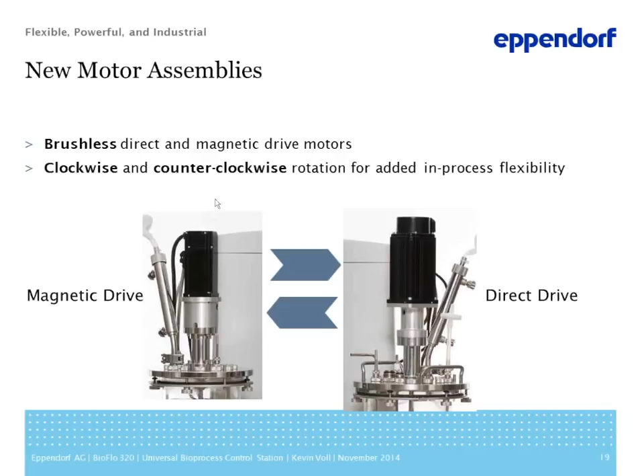In our magnetic drive motor assemblies, we now offer 3 magnetic drive motor assemblies, all using the same base motor, but with 3 different magnetic couplings for 3 different magnetic drive vessels. Our autoclavable vessels have an assembly specific to them. We offer assemblies specific to our single-use vessels, including our larger single-use vessels for the BioBLU 5, 14, and 50, and also an assembly specific to our BioBLU 1 vessels. Because they use the same base motor, we offer separate adapters, headplate adapters, and magnets that can take the same base motor and make it functional for the other vessels. So again, the flexibility is incorporated into the use of the same base magnetic drive motor as well.